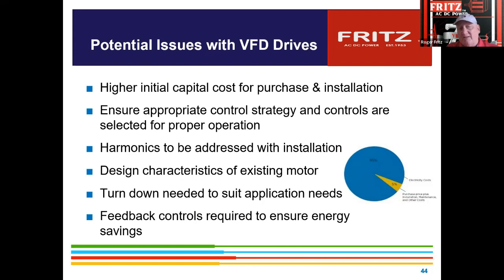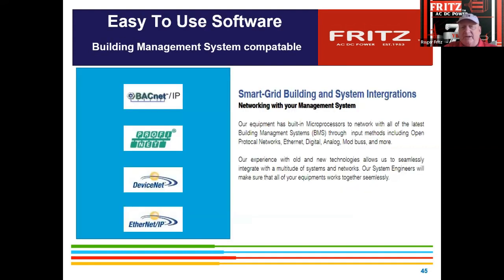So there are technologies out there that can go on the front and be active. They call it active front end equipment, that will clean it all up and give it all sinusoidal total back to the power company, which then they're happy. Their hybrid meters don't pick it up, and it cleans it up cost effectively. Again, how much can you turn it down to the suitable need? And then feedback controls. Most drives today all have both 0 to 10, 4 to 20, PLC control input, so you can program it up to the actual application. Many of them can go into the smart building integration systems, where they have BACnet, Profibus, DeviceNet.